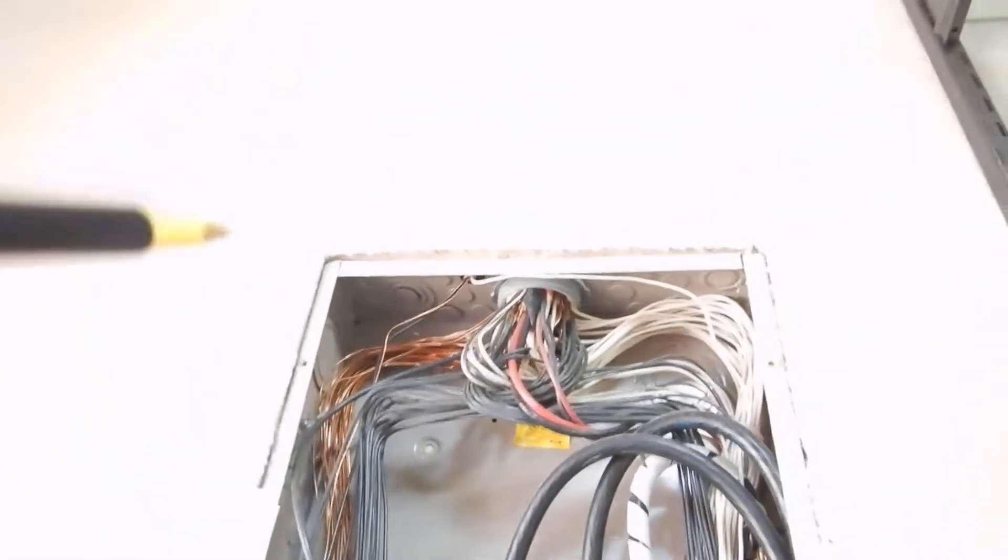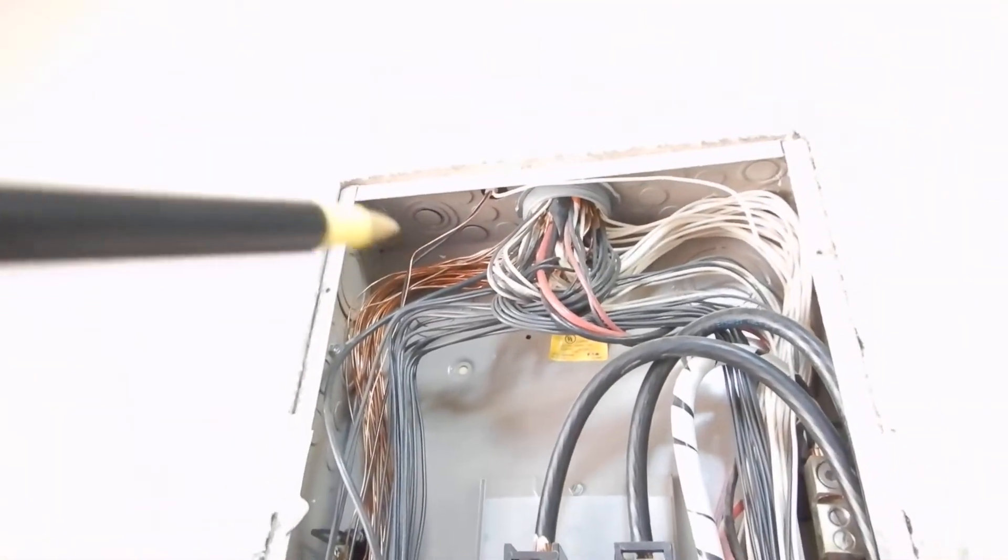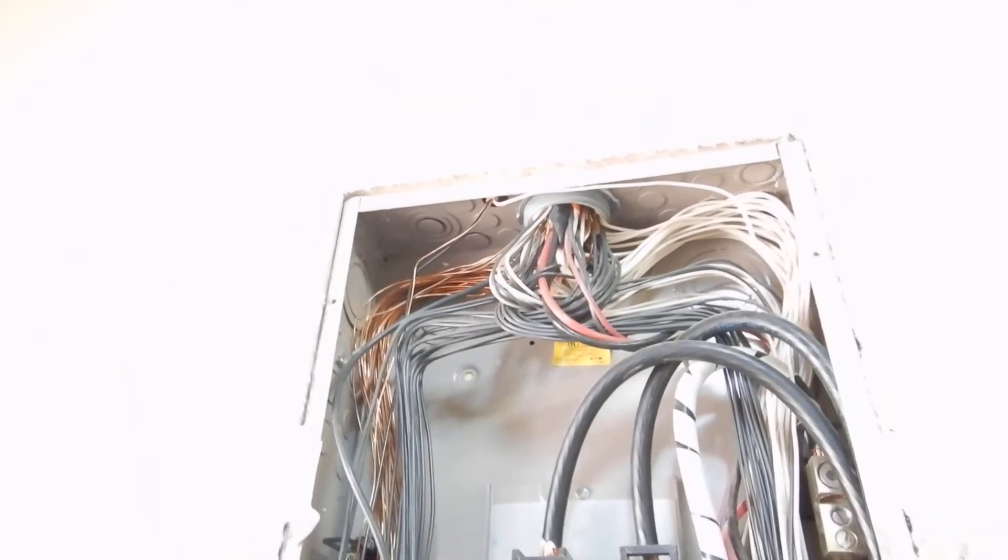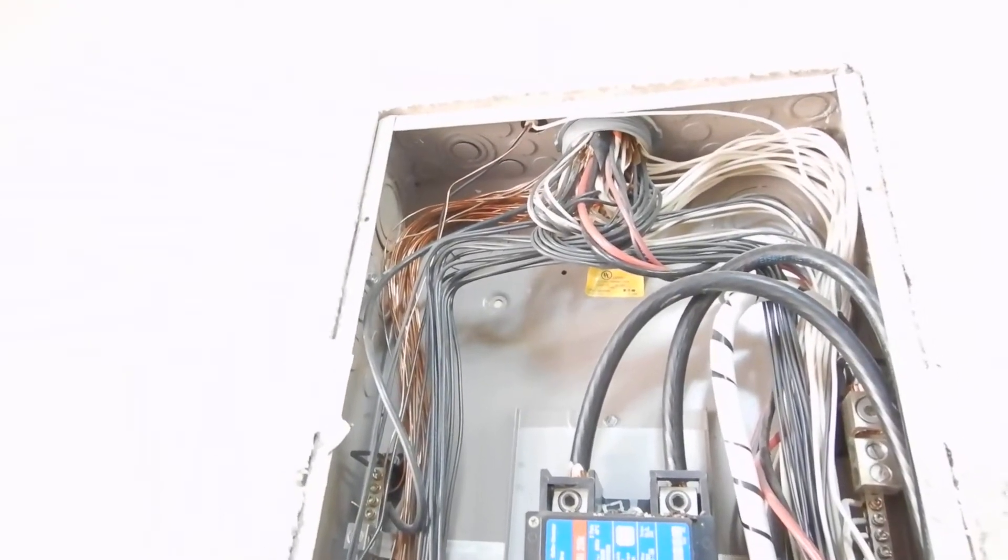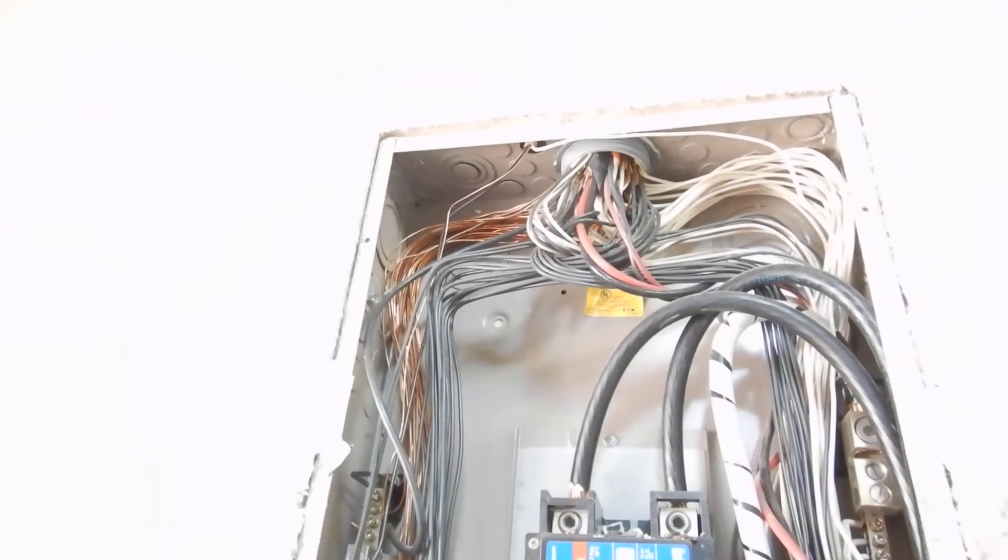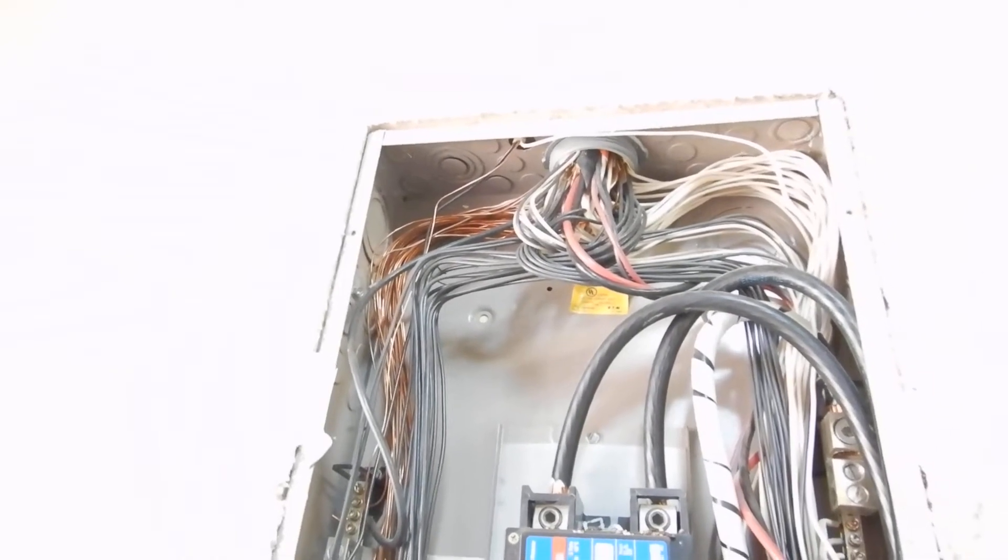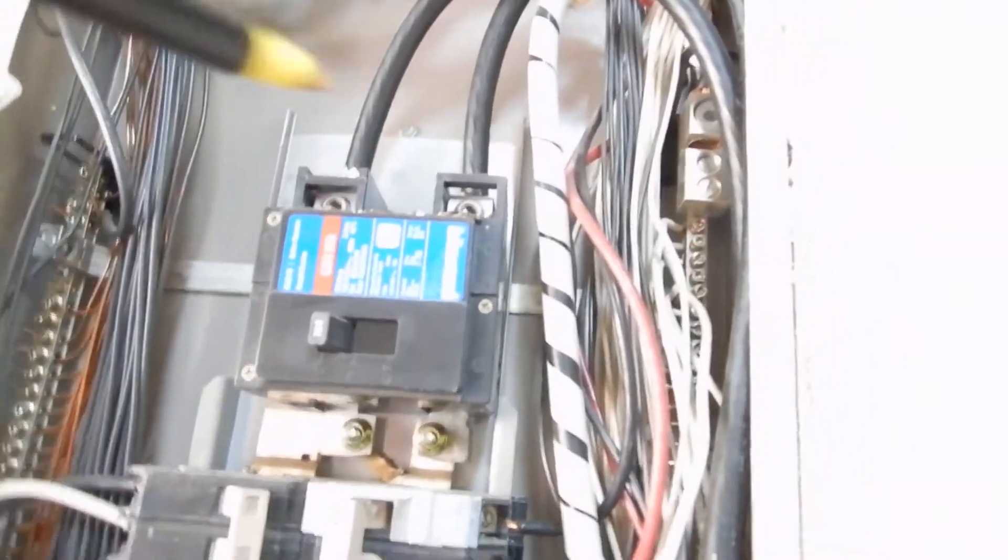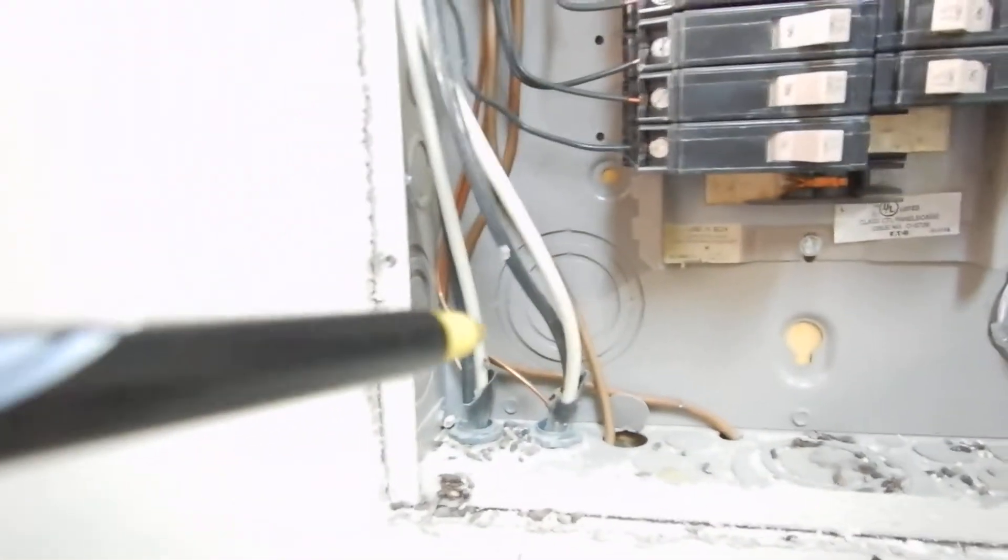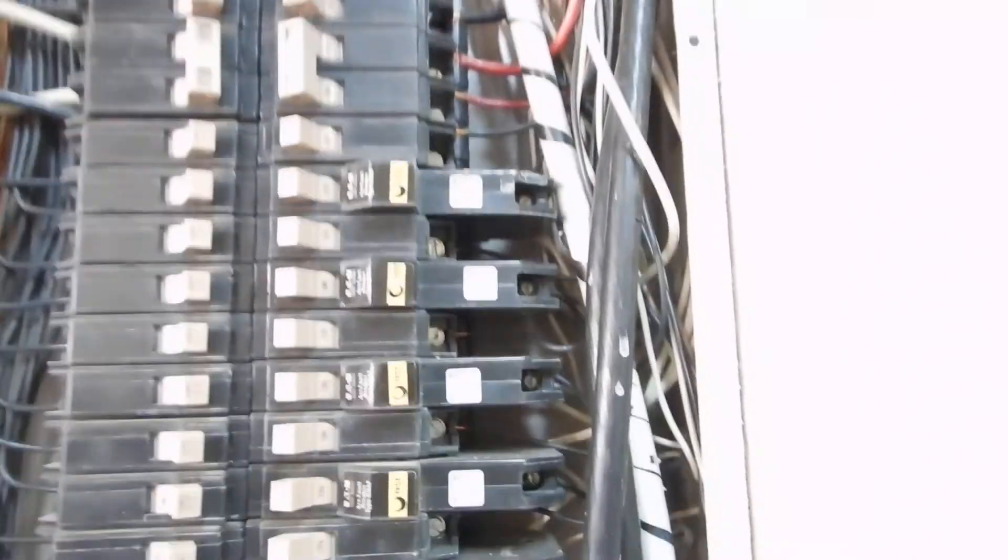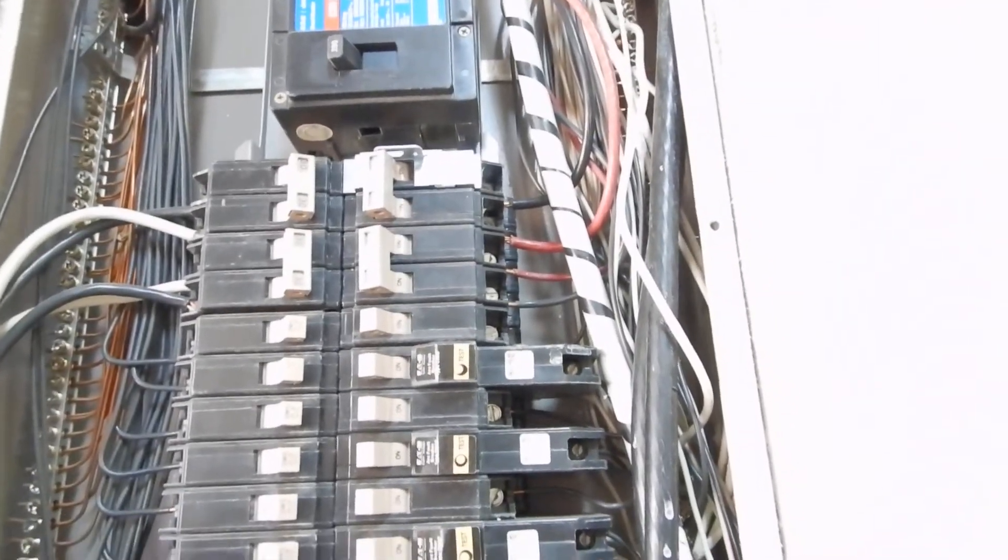Okay, all these cables coming in here, cables and wires, that's called bundling. It's very common. Even the illustration that I'm going to bake into the inspection report says it's a very common deficiency. That big hole is for L1 and L2 to come in, like right here, but the box comes off the shelf. Maybe it comes in here, maybe it comes in there. So that's why we have these knockouts here, so we can install this panel, this cabinet in different locations.